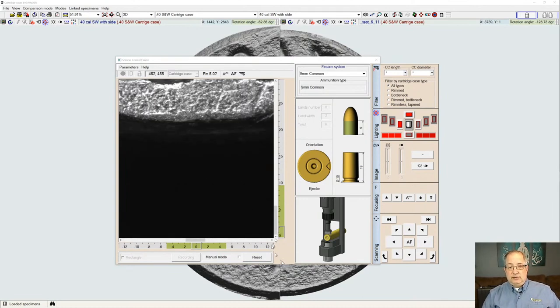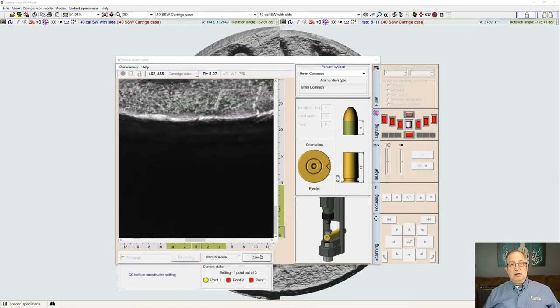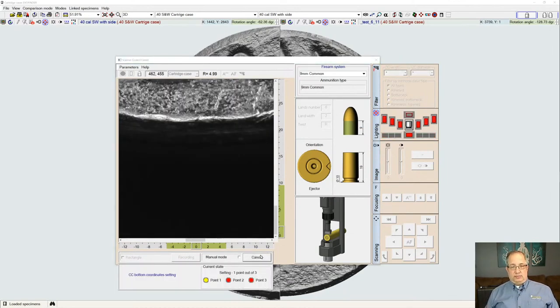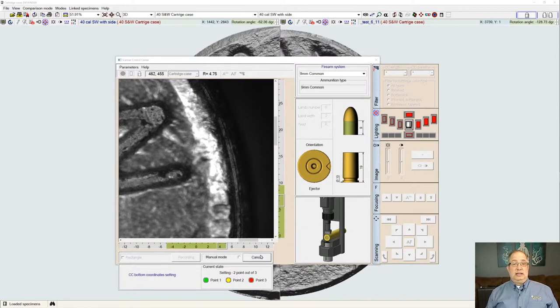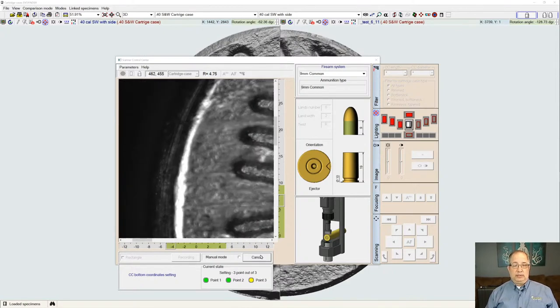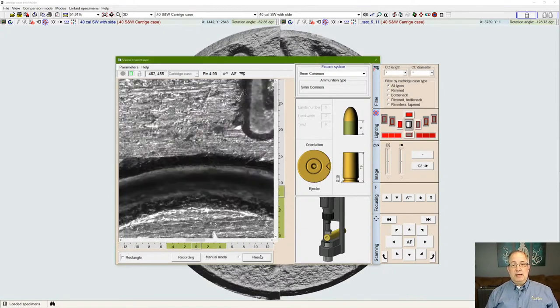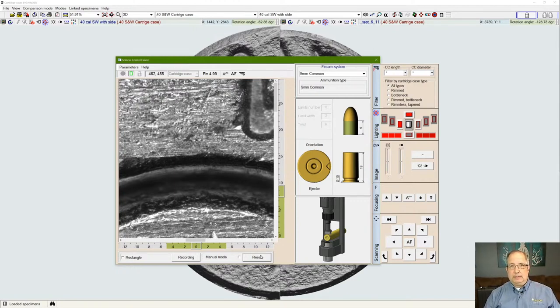Once we put a sample in there, we get a live view of what we're looking at in the chamber, but the automated software will allow us to set up the system, generate an automatic preview of it, and then set up the actual scan of the image. While the scanner works, we can actually go and do other things in the software in the background at the same time.